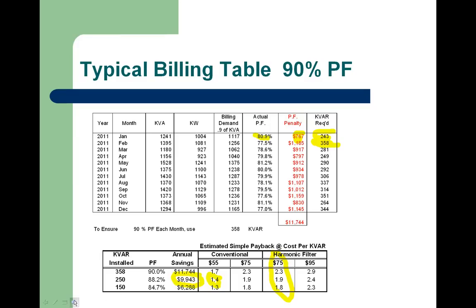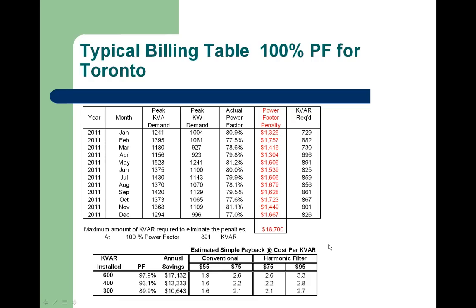We go on to the next slide. This is for Toronto Hydro, which is at Unity, and here the same thing would apply. To be able to correct to Unity, you'd need a minimum of 891 kVAR to save just over $18,000. As I mentioned before, correcting to Unity is a relatively expensive thing to do.